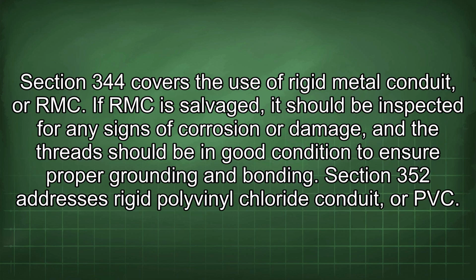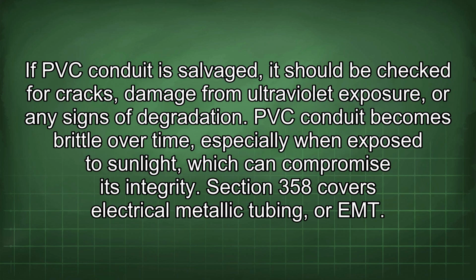Section 344 covers the use of rigid metal conduit, or RMC. If RMC is salvaged, it should be inspected for any signs of corrosion or damage, and the thread should be in good condition to ensure proper grounding and bonding. Section 352 addresses rigid polyvinyl chloride conduit, or PVC. If PVC conduit is salvaged, it should be checked for cracks, damage from ultraviolet exposure, or any signs of degradation. PVC conduit becomes brittle over time, especially when exposed to sunlight, which can compromise its integrity.